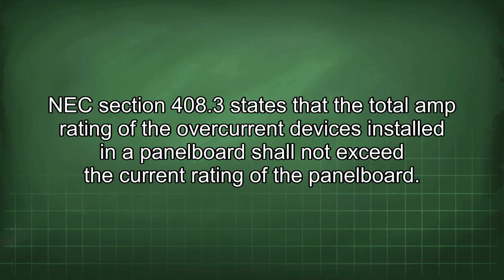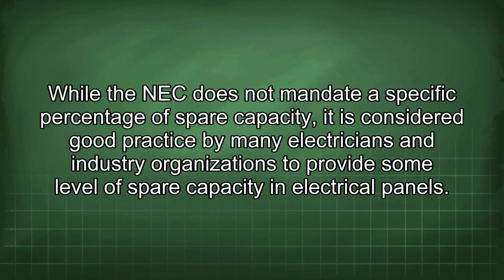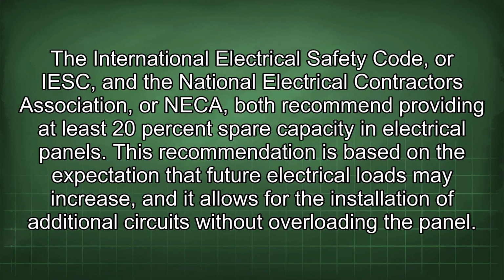NEC Section 408.3 states that the total amp rating of the overcurrent devices installed in a panel board shall not exceed the current rating of the panel board. While the NEC does not mandate a specific percentage of spare capacity, it is considered good practice by many electricians and industry organizations to provide some level of spare capacity in electrical panels. The International Electrical Safety Code, or IESC, and the National Electrical Contractors Association, or NECA, both recommend providing at least 20% spare capacity in electrical panels.